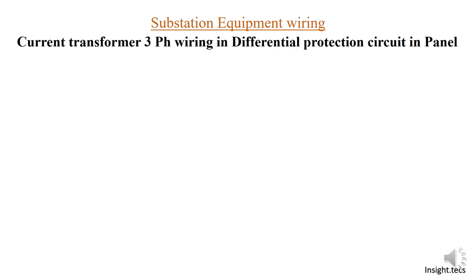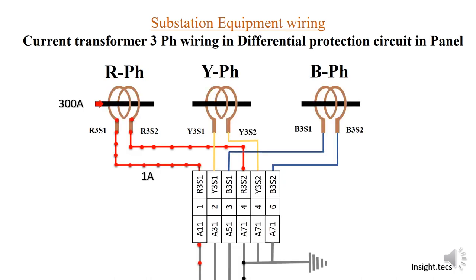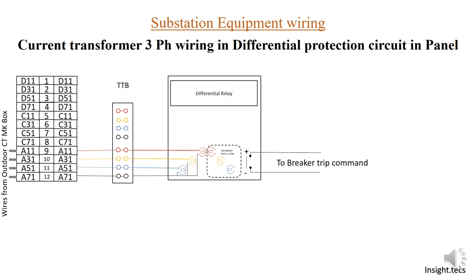The third core is the special protection core, which we use for differential protection. The third core is the special protection core used for differential protection. The wire naming convention will be A11, A31, A51, A71. In this video we will see how the three-phase wiring is. The third core is shown here, and there are four wires in the panel: A11, A31, A51, and A71. We will see how the same thing works in the panel. In the panel, there is the same TTB, and then there is a differential relay.